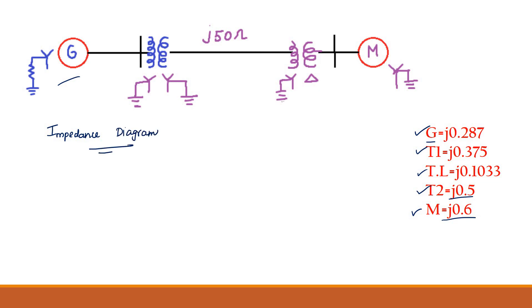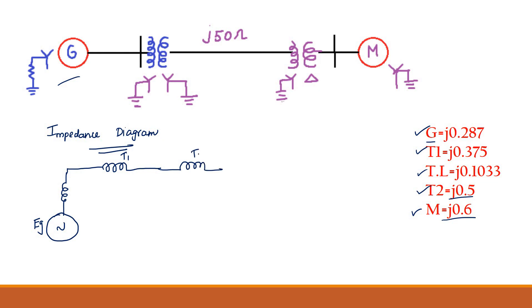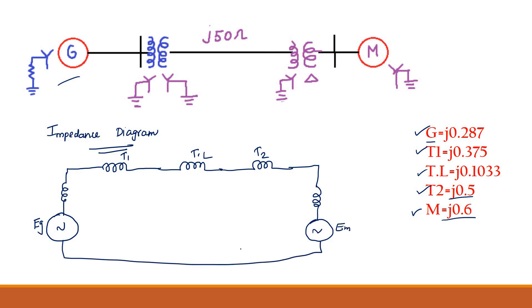The generator is represented as voltage source EG in series with an inductor (impedance). Transformer 1 follows, then the transmission line, then transformer 2, and finally the motor represented as EM in series with its impedance. The impedance values are placed one by one: generator J0.287, transformer 1 J0.375, transmission line J0.1033, transformer 2 J0.5, motor J0.6. This is the complete impedance diagram.